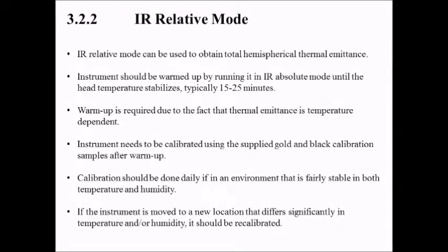IR relative mode. IR relative mode can be used to obtain total hemispherical thermal emittance. Instruments should be warmed up by running it in IR absolute mode until the head temperature stabilizes, typically 15 to 25 minutes. Warm up is required due to the fact that thermal emittance is temperature dependent. Instrument needs to be calibrated using the supplied gold and black calibration samples after warm up.